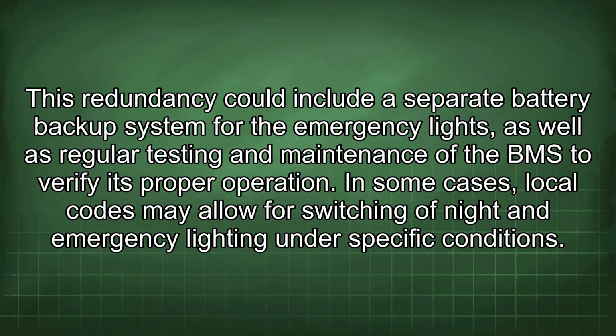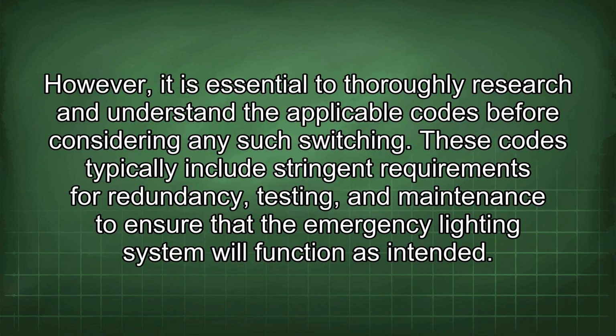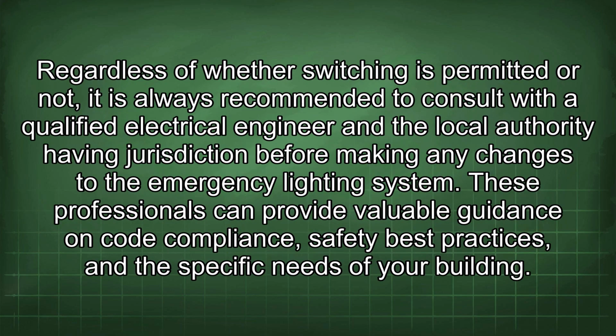In some cases, local codes may allow for switching of night and emergency lighting under specific conditions. However, it is essential to thoroughly research and understand the applicable codes before considering any such switching. These codes typically include stringent requirements for redundancy, testing, and maintenance to ensure that the emergency lighting system will function as intended. Regardless of whether switching is permitted or not, it is always recommended to consult with a qualified electrical engineer and the local authority having jurisdiction before making any changes to the emergency lighting system. These professionals can provide valuable guidance on code compliance, safety best practices, and the specific needs of your building.